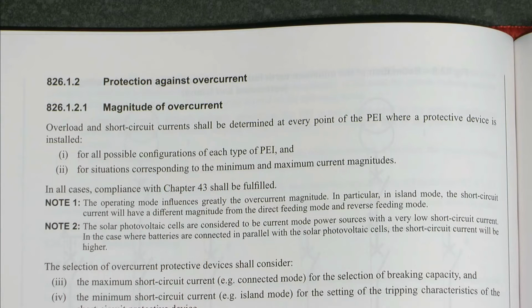But if you then switched over to running from your batteries, that is a totally different kind of supply, and where that's actually coming into your system isn't going to be the same point as where the electricity from your grid connection comes in. So the location of protective devices has to be considered, because protective devices good for one type of supply may not be suitable for another. So you may have to put in additional devices to cover when you're running from your batteries or via an inverter, and the same applies to things like solar panels.